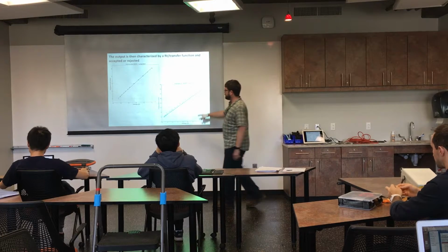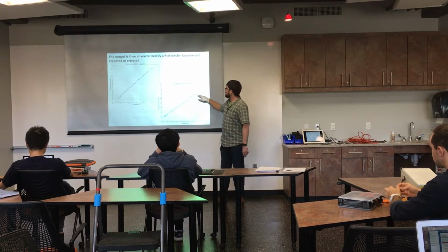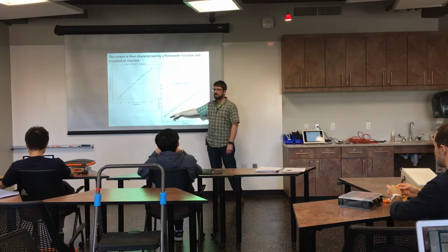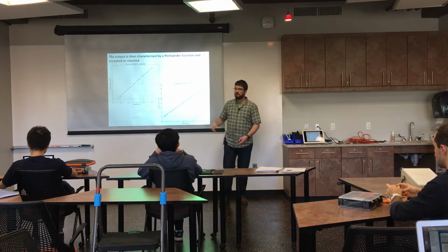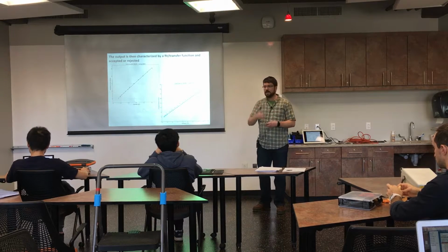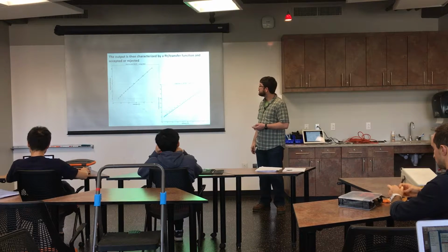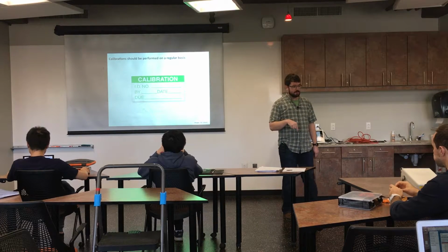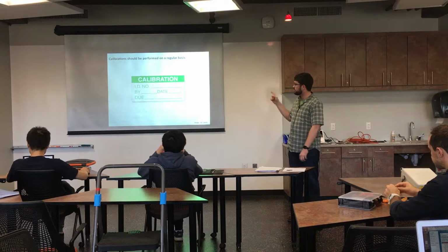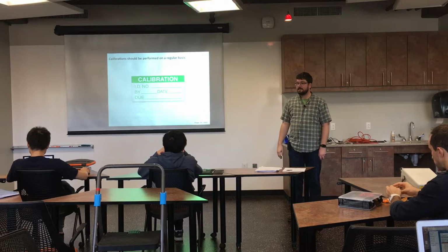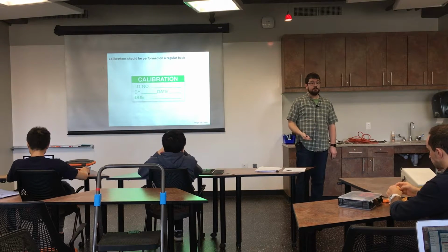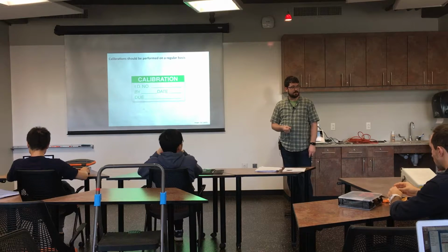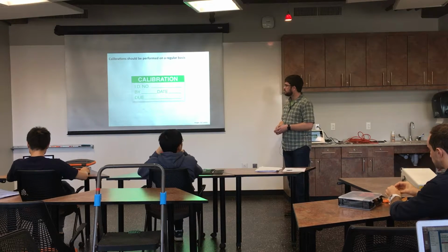Another thing, if you do see this, think about, did somebody do it up to here and then they go to lunch and somebody else start using the vernier scale on the way back down? You could have some kind of different bias in how you're adjusting things. And the calibration needs to be performed on a regular basis. Normally in industrial settings, you'll see these stickers on things that say when the calibration was done and when it's due. So semi-annually or annually is a pretty good number for most things. There are some instruments that you can go a few years on.